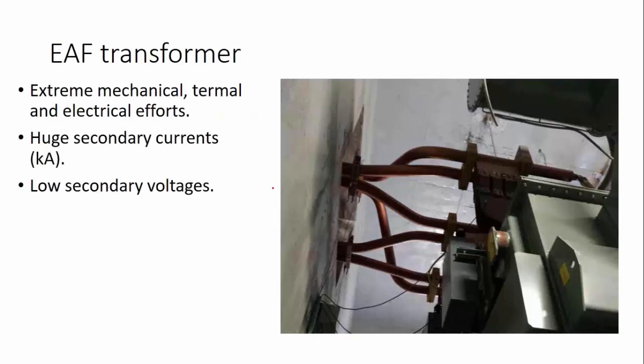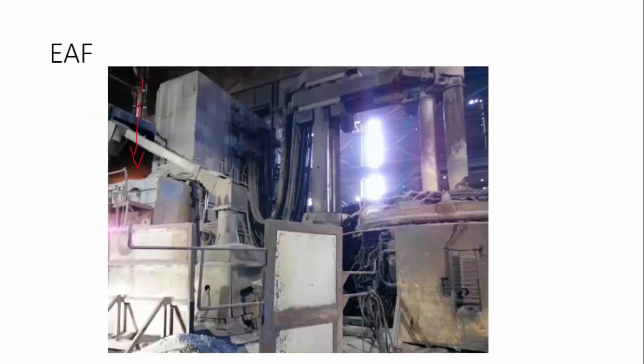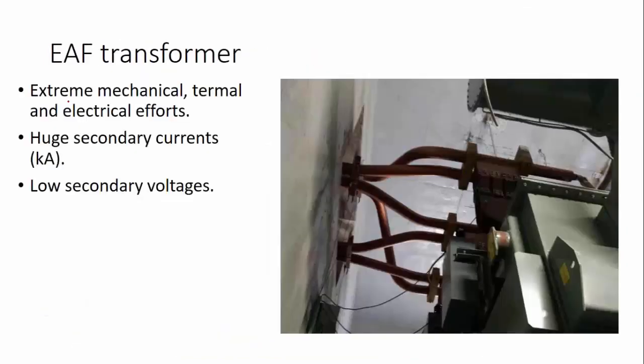Now, when you get closer to the oven, I'm going to go to my first picture. When you get to the transformer that is exactly right behind the furnace, you will find a very specially designed transformer, an electric arc furnace transformer that can handle huge secondary currents, 10, 20 kiloamps, because it's a lot of power at very low voltage. So these transformers are specially designed because they are subjected to extreme mechanical, thermal, and electrical stresses. The voltage on the secondary of this transformer goes from around 660 up to 1000 volts. This is a typical secondary. So you may find this very low in comparison to the main voltage for this transformer, which is 34.5 kV. So it's quite a difference in voltage, quite a difference in current.